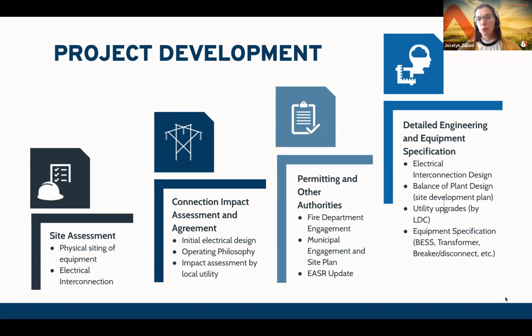Finally, we move into the detailed engineering and equipment selection phase. This phase involves detailed design of the electrical interconnection and balance of plant, as well as engaging with the utility to understand what upgrades they need and making sure our design considers those upgrades and that their design is progressing. Then we select the equipment, not only the battery but the transformer, interconnection equipment, and communications equipment required for interface between the battery and the local distribution company.